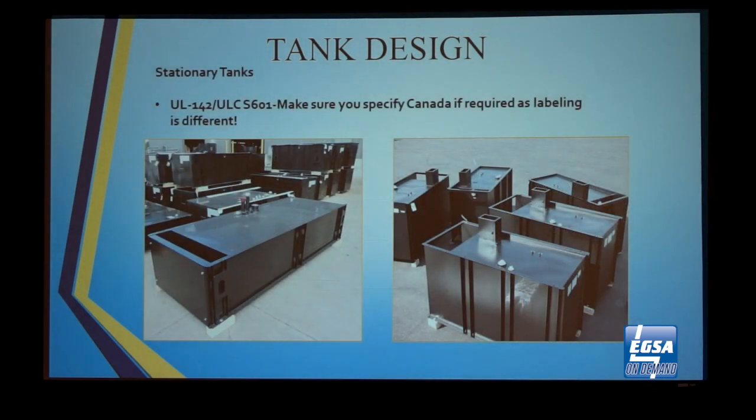As far as UL tanks, there's UL 142, ULC S601, and UL 2085. It's important to know which certification is required in your area so you don't have unnecessary costs — such as a generator showing up on a job site and the AHJ rejecting it because it's the wrong UL listed tank. It's important to specify U.S. or Canada as some tanks are labeled for one or the other. The interstitial space on a UL 2085 tank is filled with concrete to be fire-resistant and impact-resistant. UL 2085 is not commonly required but is gaining popularity in higher-risk applications.